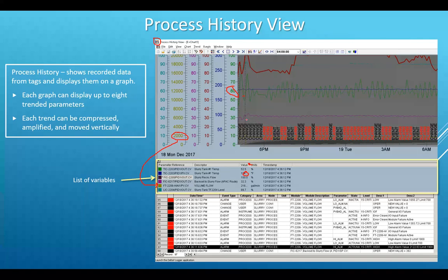Also, you'll notice all these change, alarm, event entries on the bottom. Now they seem to all pull all the way back to here, so they try to touch here, right? So something big happened right here, so you can go down and see, okay, everything happened at 4:36 p.m. on this date, and there was an alarm or an event or a change, and it'll try to tell you where it happened, and then what happened, who did it. So there's a new value here. Somebody changed the value. Who changed it? The operator did. Now that'd be your name if you're logging in with names. It'd be, say, Carson Merkel, and he changed that. Those types of things are pretty useful when you're trying to troubleshoot or trying to figure out what opportunities you can take advantage of.